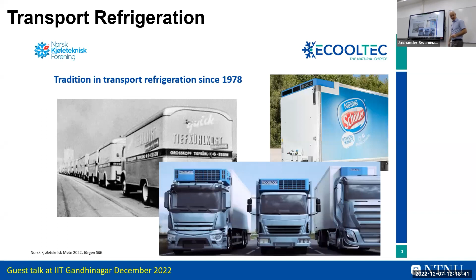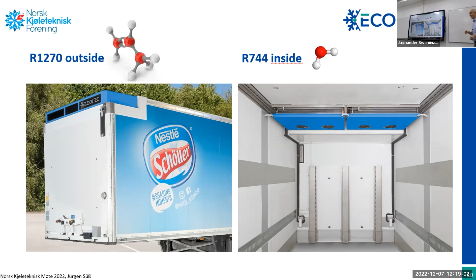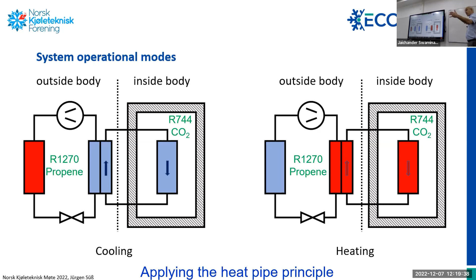They do a combination system with propene, no F-gas, on the roof outside, very efficient and energy efficient, and on the inside CO2, but no pump, just thermosiphon, and it works very good. The CO2 is evaporating here, condensing here, and circulating for cooling. In heating, it's the opposite, condensing here and rejecting the heat. No pump, nothing, but it works. Very compact. The flammable stuff is on the outside, never in the compartment, so if a leak happens, no problem.